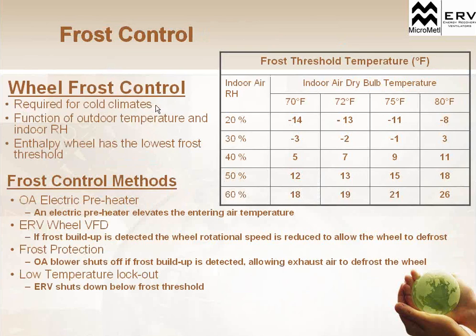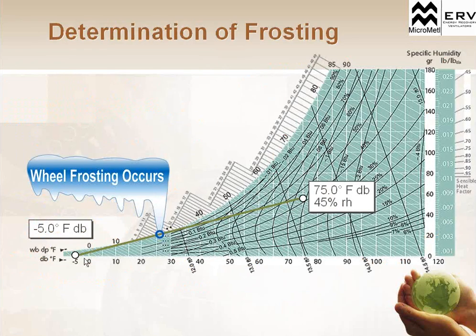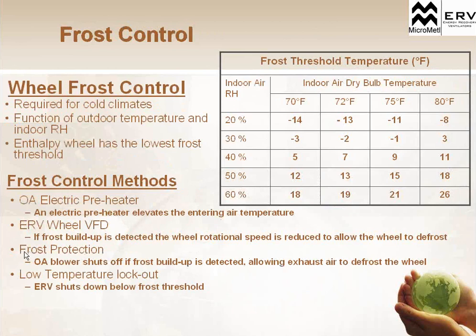Some wheel frost control is obviously required for colder climates. The enthalpy wheel has the lowest frost threshold because it has a way to mitigate some of that humidity. Some of the frost control methods I just mentioned were an outside air electric preheater. So you can actually preheat the air coming in, which would move this entire line over, so we wouldn't be crossing that dew point line.